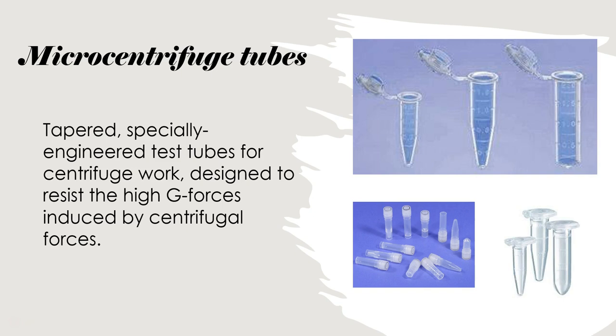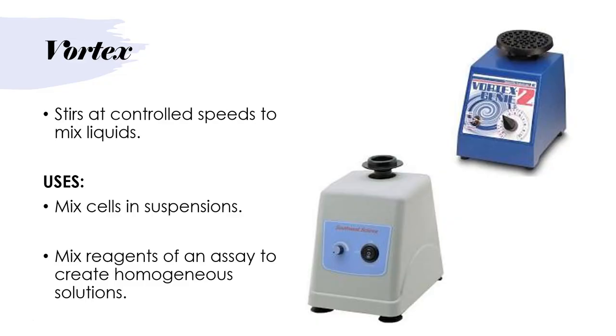And for macrocentrifuges, you can have tubes that are 5 ml, 10 ml, 15 or 50 ml. All of those tubes can be used in those systems. Other times we are doing experiments where we don't need to separate our sample, but rather we want to create a homogeneous solution or suspension. If that is our goal, we use a vortex.